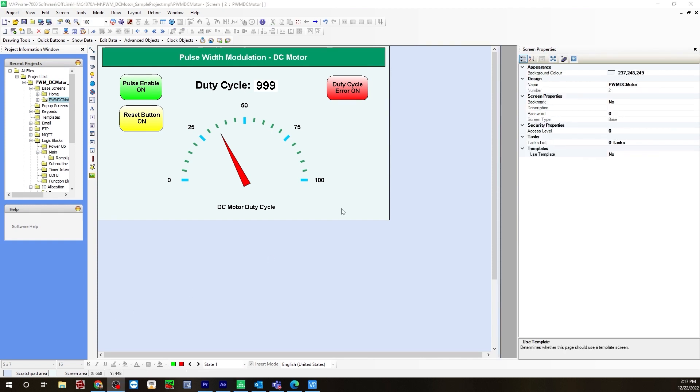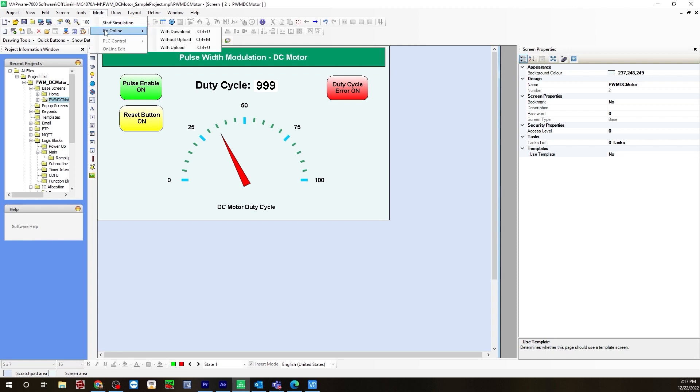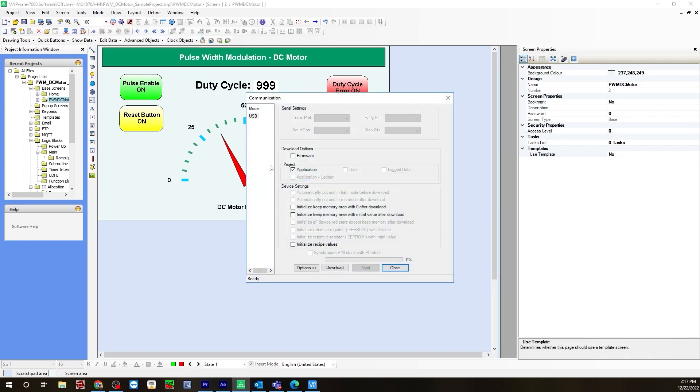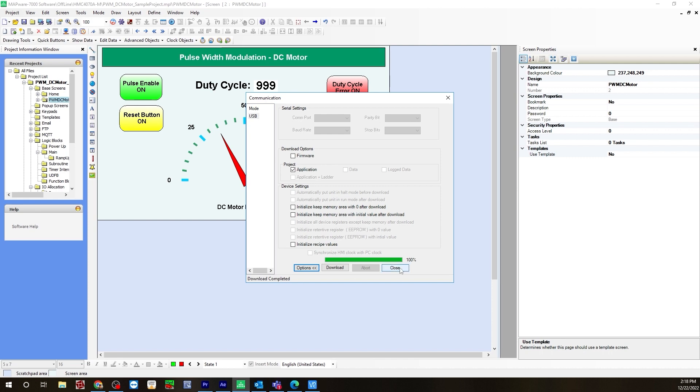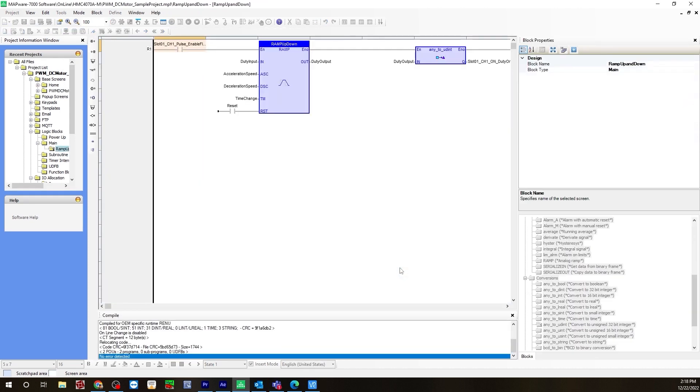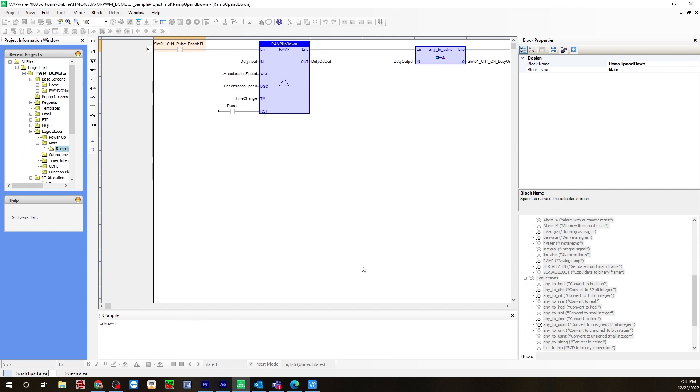Once you've finished creating the base screen, you are now ready to download and go online. Go up to mode, go online with download. If you're downloading for the first time, make sure you have firmware checked off. In this case, I've already downloaded once, so I just need to have application checked off. Hit download. Download completed, hit close. Now it may take a few seconds for the HMC device to load the application. Once it does, in the compile window, it will say run, and you know you're online and everything is working.